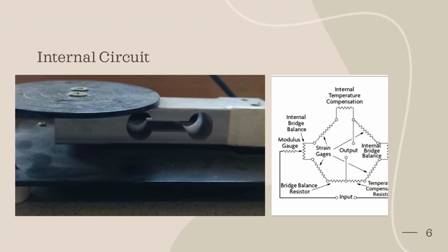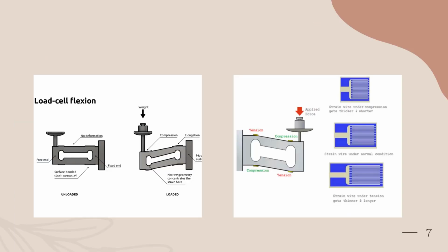We will discuss the internal circuit and working of the load cell. As we know, the strain gauge load cell converts the load acting on it into an electrical signal. The gauges themselves are bonded into a beam or structural member that deforms when the weight is applied. In most cases, four strain gauges are used to obtain maximum sensitivity and temperature compensation. Two of the gauges are usually in tension and two in compression, and are wired with compensation adjustment, as you can see in the figure.